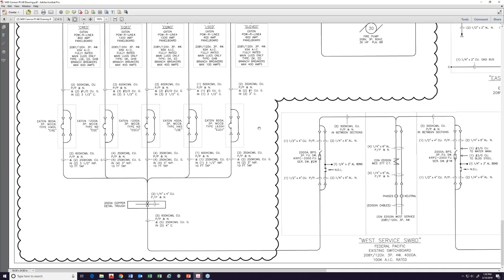Now, in the utility side, you can put all of these devices into one panel board because the code does not require separation. Happens to be in this particular design, it worked. It was more economical to do it in separate enclosures because of some existing field conditions. And again, every single job will be different and requires different solutions. This is just the way we did it on here, and it works great.